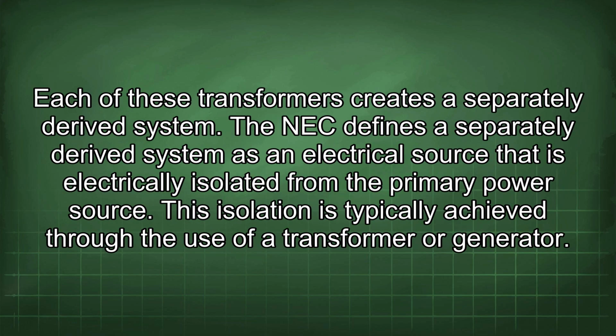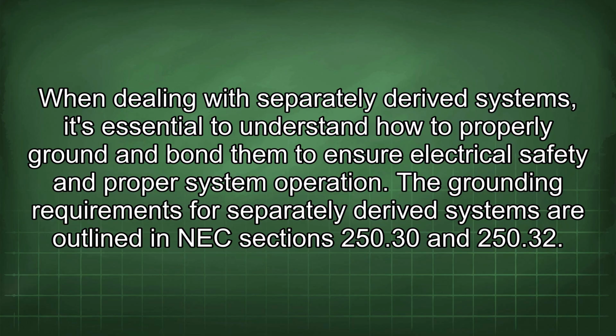Each of these transformers creates a separately derived system. The NEC defines a separately derived system as an electrical source that is electrically isolated from the primary power source. This isolation is typically achieved through the use of a transformer or generator. When dealing with separately derived systems, it's essential to understand how to properly ground and bond them to ensure electrical safety and proper system operation.